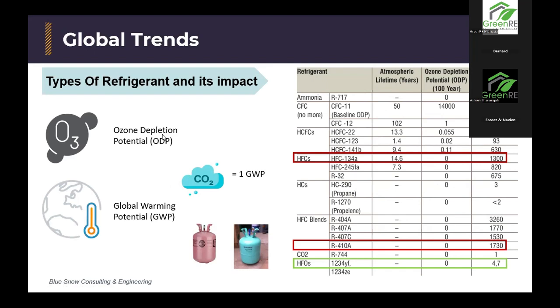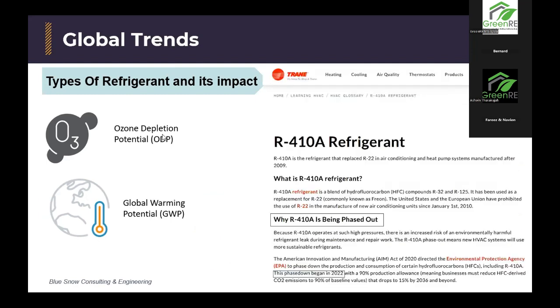So in recent years, there's been a push, because previously people only cared about something known as ODP, ozone depletion potential. So that's why you have the banning of R22, that can cause those ozone depleting problems, like those CFCs you see on the table. But now in recent years, they're also trying to reduce the GWP, the use of refrigerants with high GWP. That being, for example, R410A.